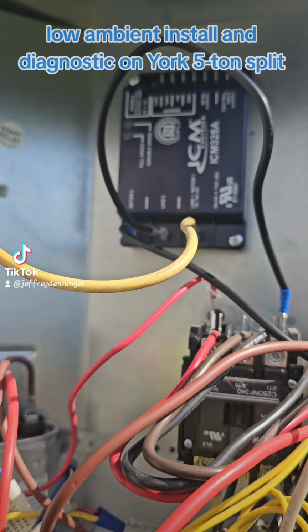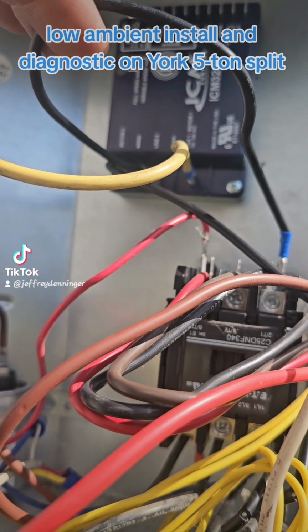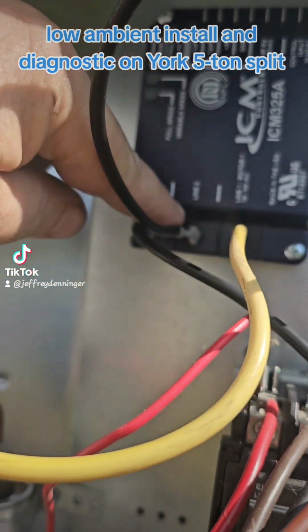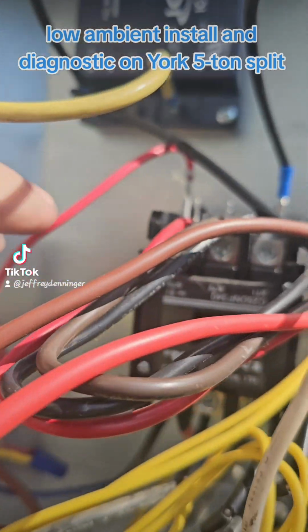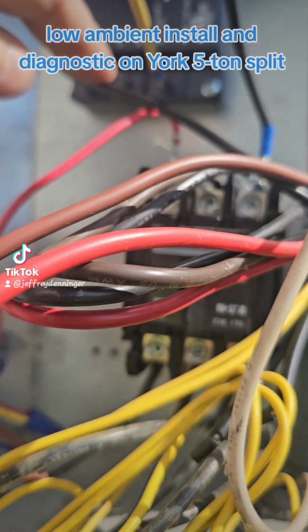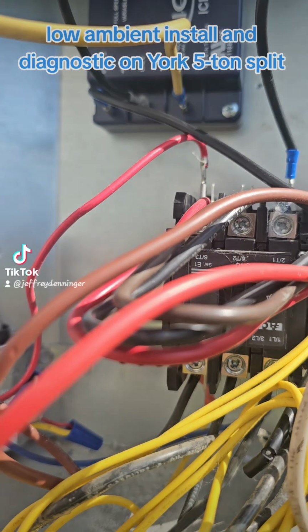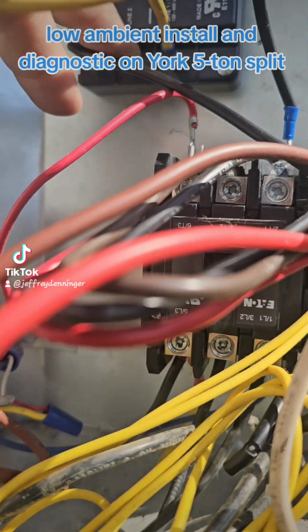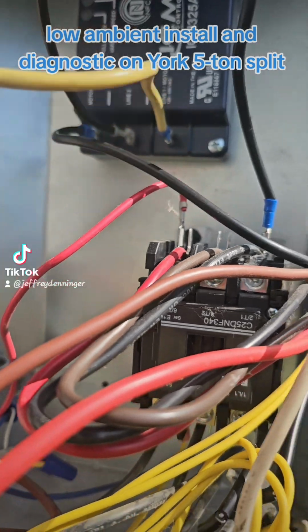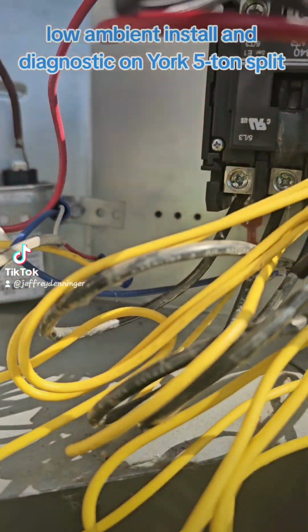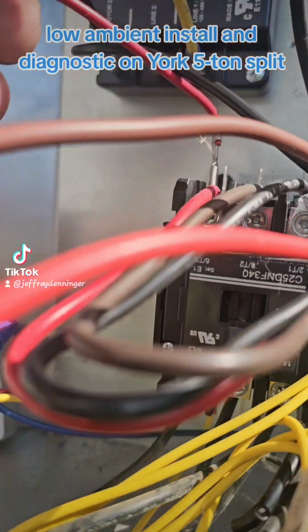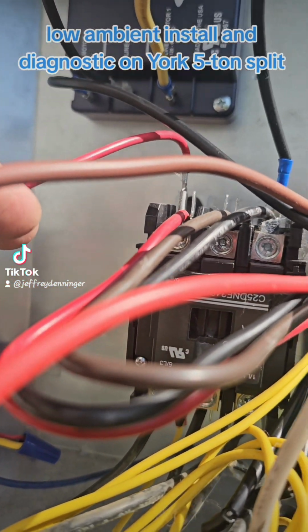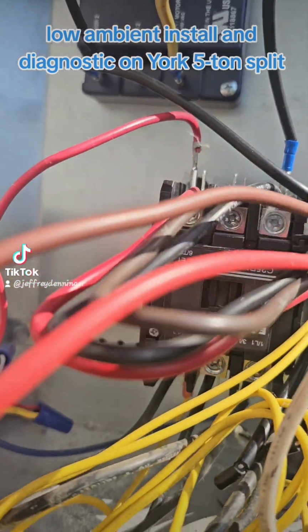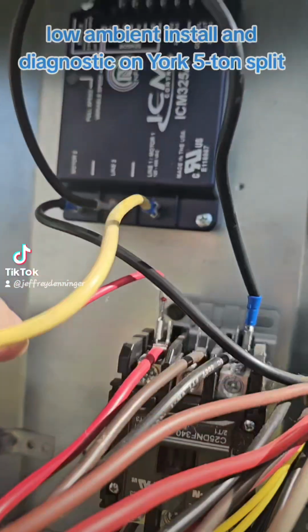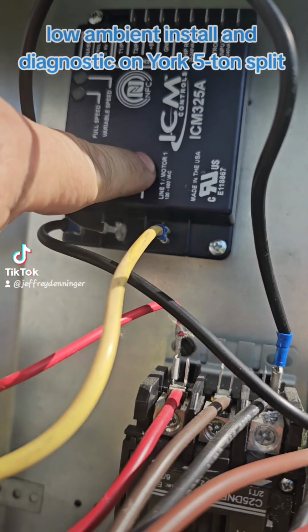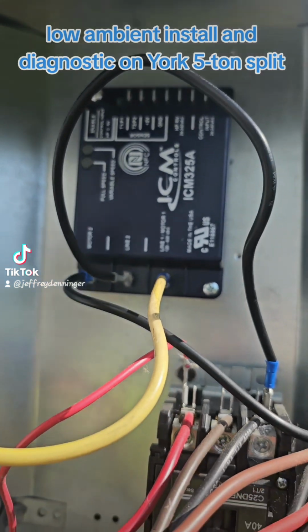Okay, we got the line side and the fan motor connected. This is feeding line 2. Then this goes out to our fan. This one goes to our reds, which is the other side of our contactor since this is 208. Goes out to the fan, but also feeds line 1 and motor 1. You'll see that on the instructions.